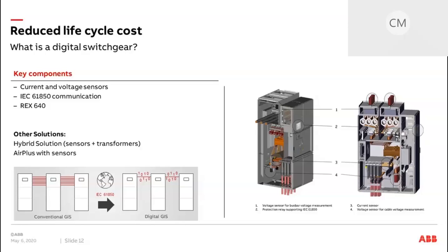These sensors for voltage measurement can be both mounted on the bus bar as seen on top on the right-hand ZX2 panel or at the bottom on the cable side. The relays would be mounted inside the LVC, and then they can be combined with monitoring diagnostic features such as temperature or ambient sensors.